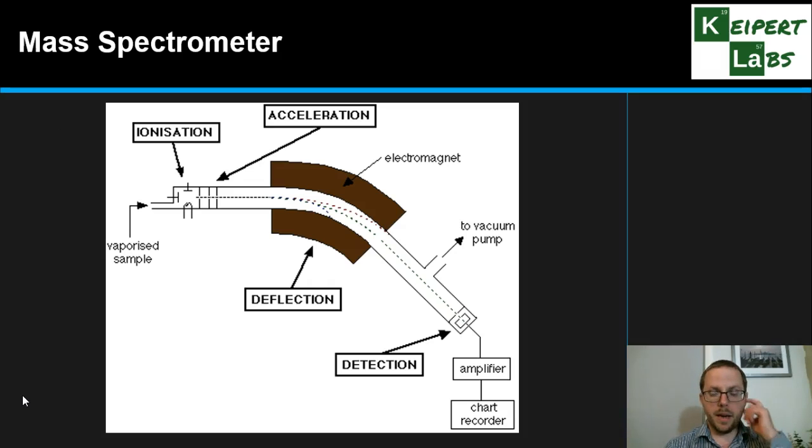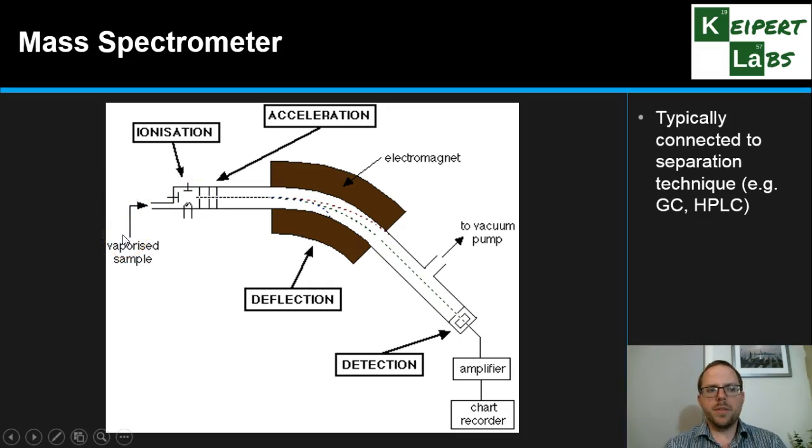Let's start by looking at this diagram of how a mass spectrometer is put together. On the left-hand side, we have where the vaporized sample enters. Typically, a mass spectrometer is connected to a separation technique like gas chromatography or high-performance liquid chromatography (HPLC), but it doesn't have to be. You can directly analyze the sample as long as it forms a vapor.